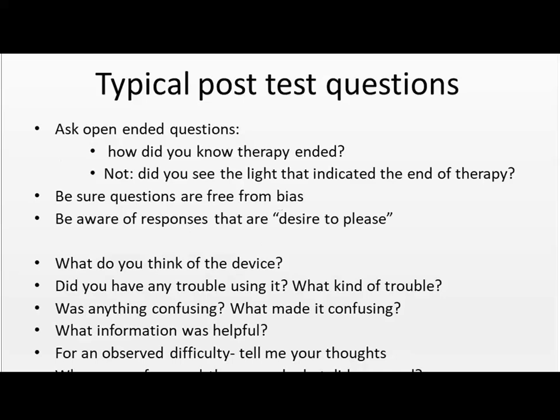You should be sure the questions are free from bias and beware of responses where the participant is trying to please the moderator, not being critical because he wants to please the moderator. Ask, what did you think of the device? Did you have any trouble using it? What kind of trouble? Was anything confusing? What made it confusing? What information was helpful?